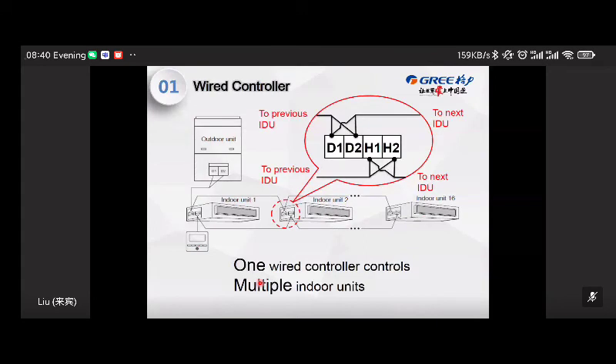And this is the wiring for one controller controlling multiple indoor units, right? It's very easy. You can just connect one controller to the H1, H2 terminal of one indoor unit, and the others you can just hook them by the cable together. And the maximum quantity is 16 indoor units. You can control them with only one wired controller.